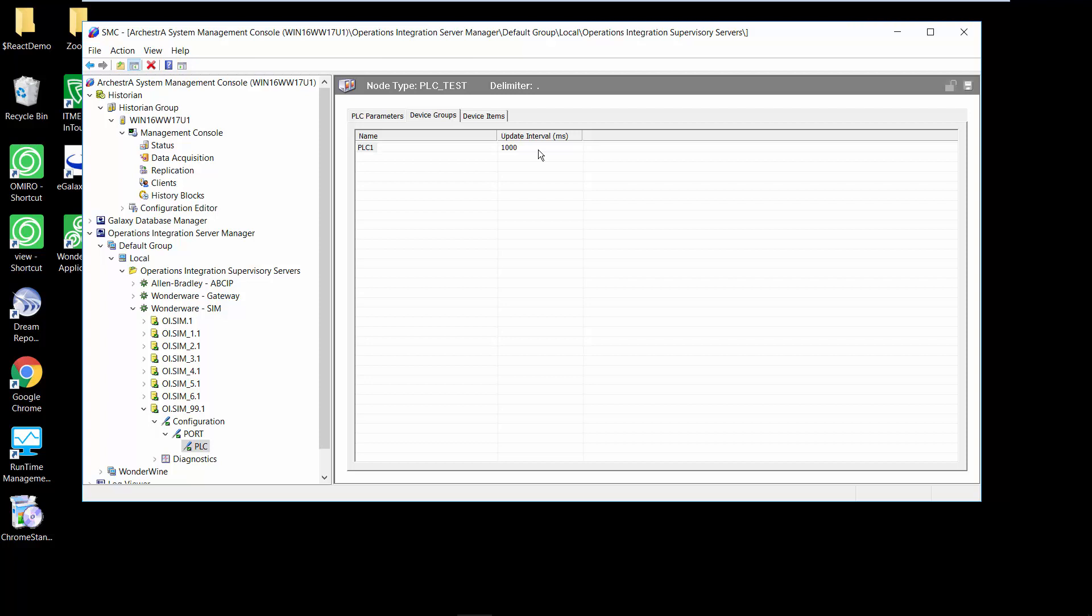The default right here is set up for a thousand milliseconds but this is the parameter that's exposed to us at runtime that we can change so that's what we're changing on the fly to go out and pull that data from the PLC at a faster rate.